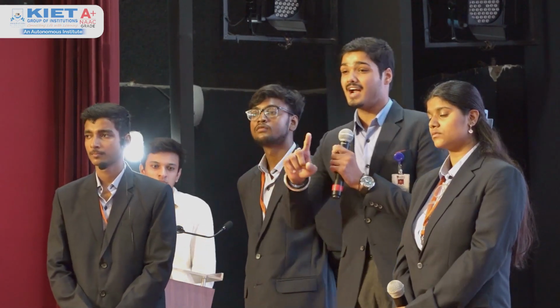Can you let us know something about calibration with native units, or calculation of measuring instruments? Let's suppose, as we mentioned, a reading of vernier caliper in our equipment - here is an example of calibration. If the vernier caliper shows 0.00 exact mm, it is good to go, but if it has any minimal zero error, we add that calibration factor to get accurate results. When we take a reading, we add that to our final reading to get accurate results. Let's take a rough example of calibration, as we've seen with weights - over time they sometimes get loose or lose weight, so we send them to be recalibrated and fill in some material to get recalibrated.